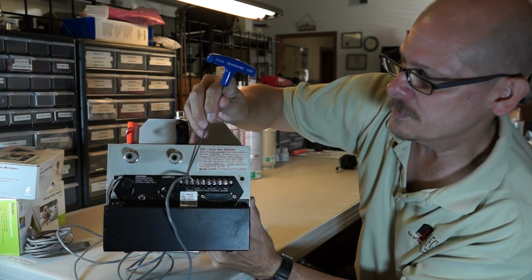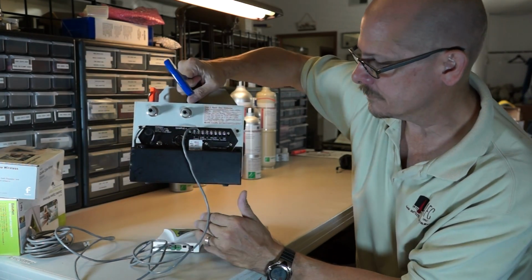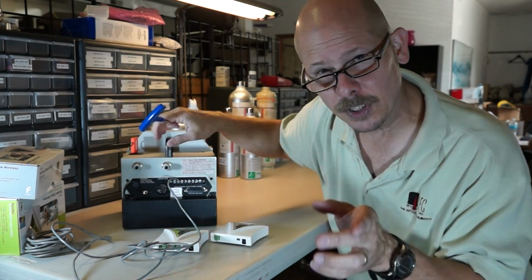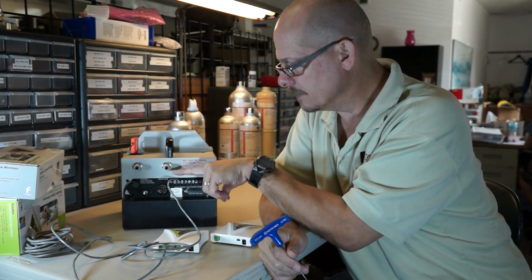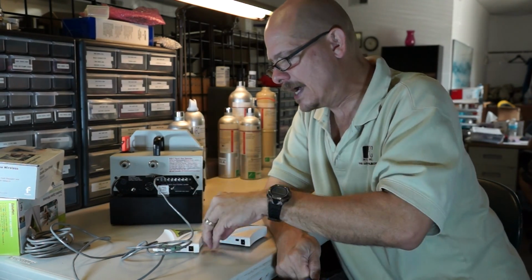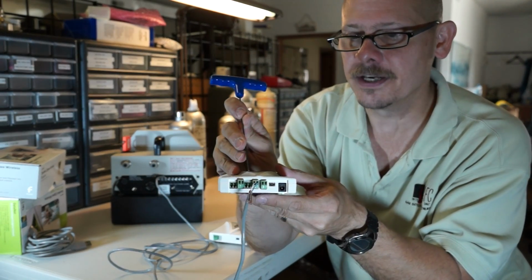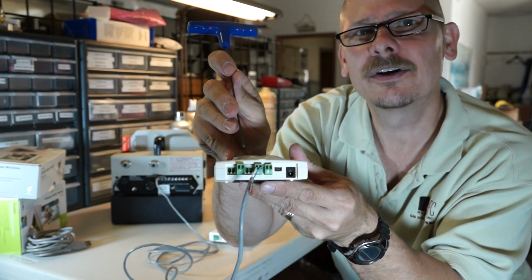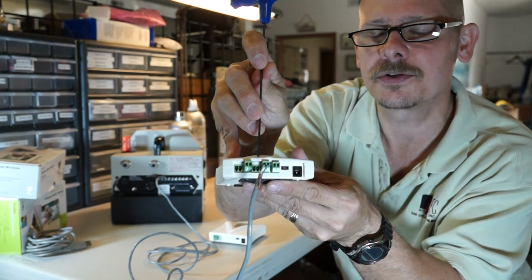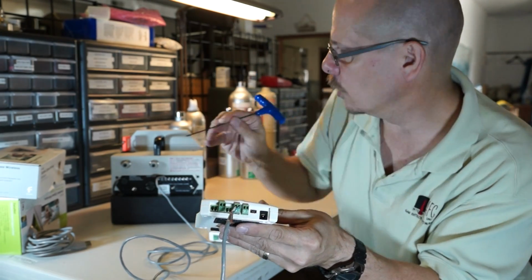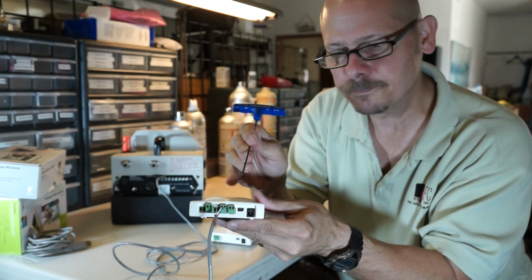A lot of older instruments have it on the little screw connections. Some will be slightly different. But that 4 to 20, you'll see a plus and you'll see a minus. And what we're going to do with those wires, we're going to put 2 wires on it. We're going to run it back to our DataNet device. And on our DataNet device, I don't know if you're going to be able to see this or not, but trust me, there is a plus and a minus on these green connectors. So we take the appropriate plus and minus from the instrument to the appropriate plus and minus on the DataNet.